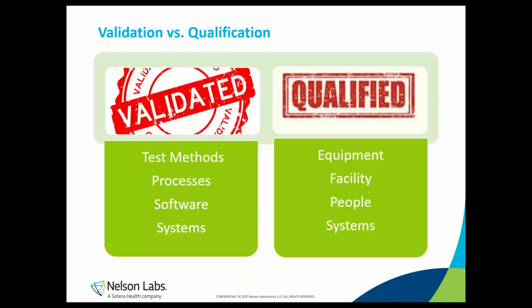Now, there's a bit of gray area here and there, and some things can fall into both categories. Regardless of whether it's a qualification or a validation, the exercise needs to be repeated periodically, and the frequency of revalidation or requalification will depend on risk and should be included in the validation plan, meaning you decide ahead of time how often you will revalidate and state why that interval is appropriate for your case.